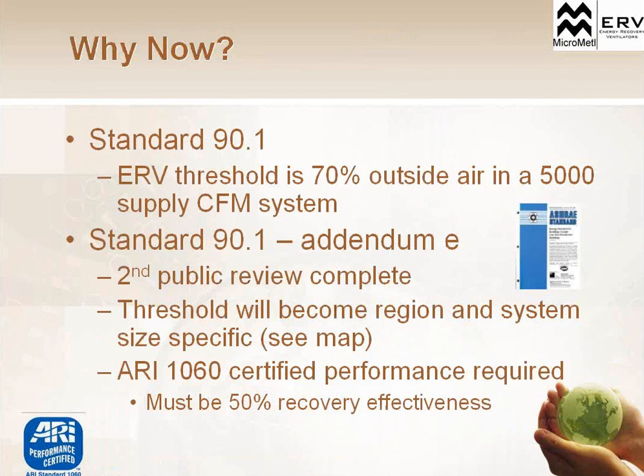So why now? Right now, what's going on is that the standard 90.1, previous to addendum E, had a threshold: whenever you have a system of 5,000 CFMs and you're bringing in 70% of that as outside air. So 70% of 5,000 CFMs, if you're bringing in that much outside air, you had to have an energy recovery unit.